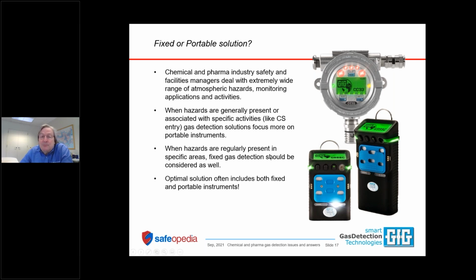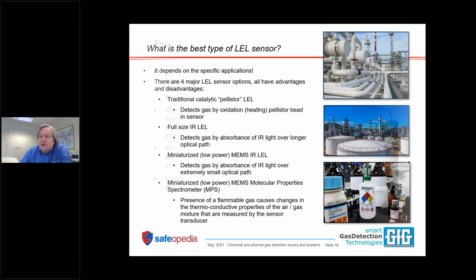When the hazards are present in specific areas, either potentially or on a regular basis, then you should definitely think about fixed gas detection. For instance, in our earlier example, if you've got a room with 3 or 4 industrial sized dewars full of liquid nitrogen, then you best have a fixed monitoring system. You wouldn't really want to deal with that hazard only with the issuance and use of personal oxygen meters. So often the best solution includes both fixed and portable. It all just depends on what's going on in the area.